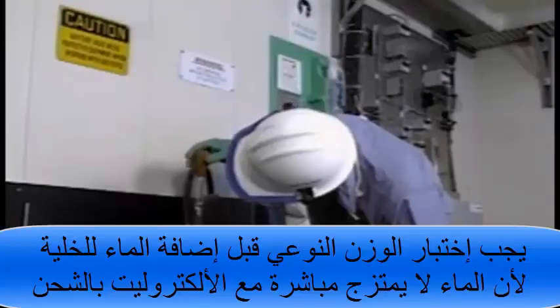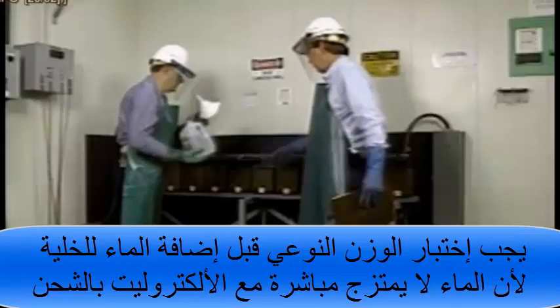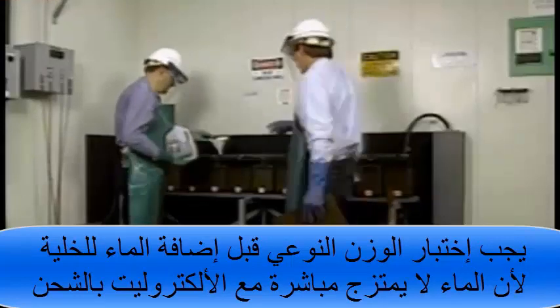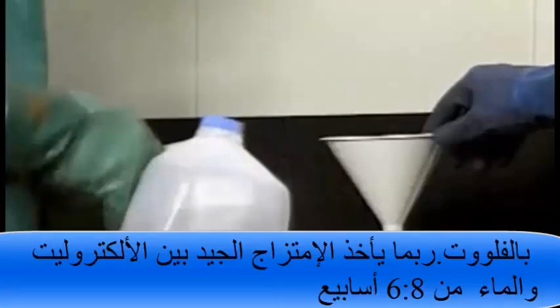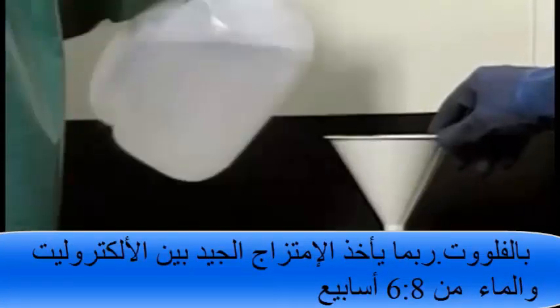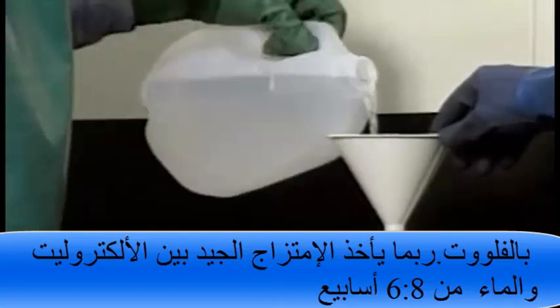Specific gravity should be checked before water is added to a cell, because the water doesn't immediately mix with the electrolyte. Under normal float charge conditions, it may take 6 to 8 weeks for the water and electrolyte to thoroughly mix.